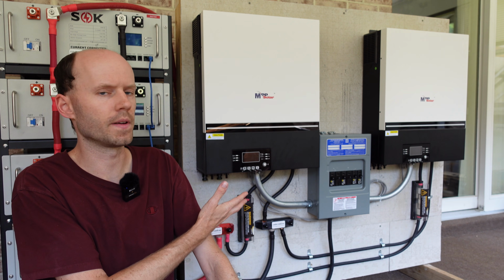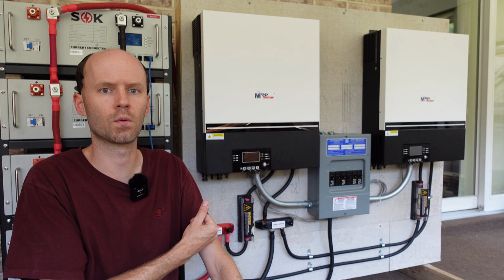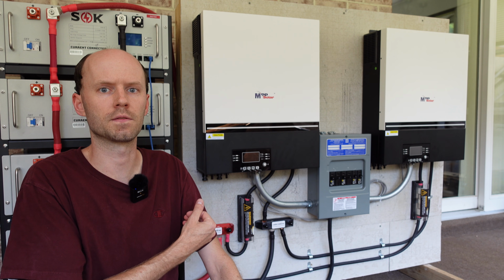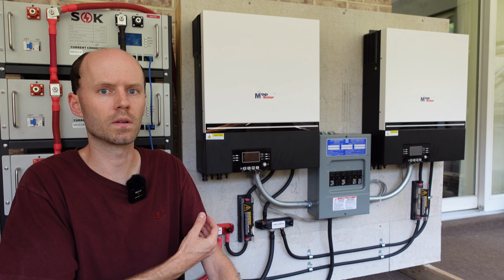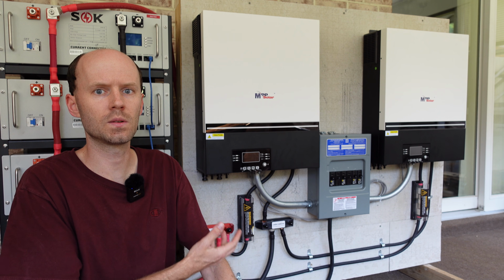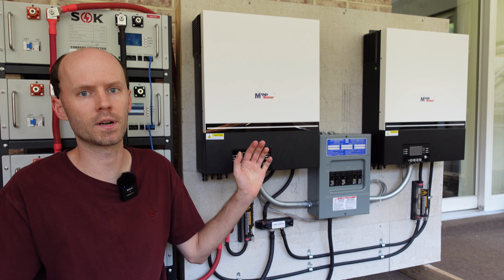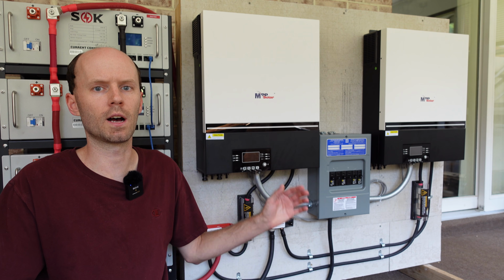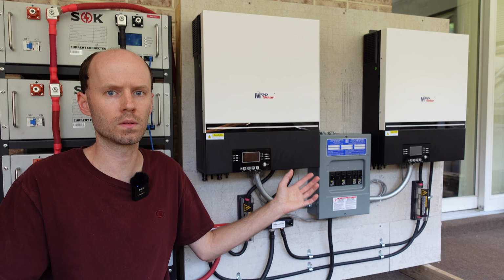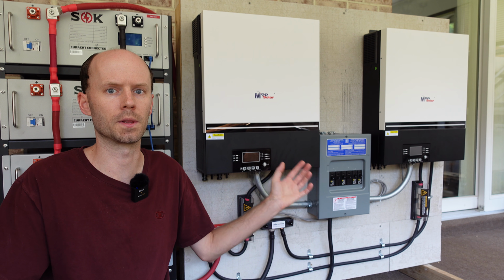I have a pair of MPP Solar LV6548 inverters. They are 6,500 watts each. So we're going to set up the battery wiring, the AC wiring, and have these operating in split phase mode. That means it will output both 120 and 240 volts, which is the standard here in North America in the United States.